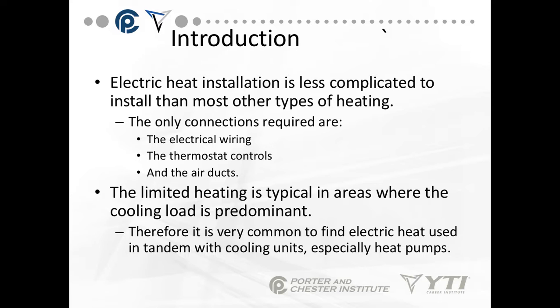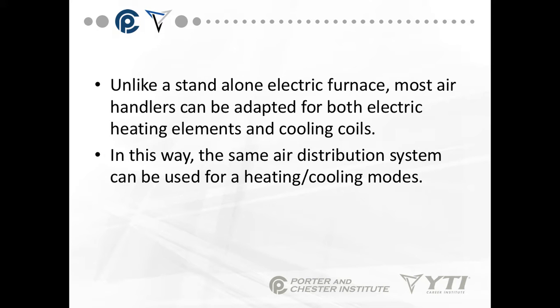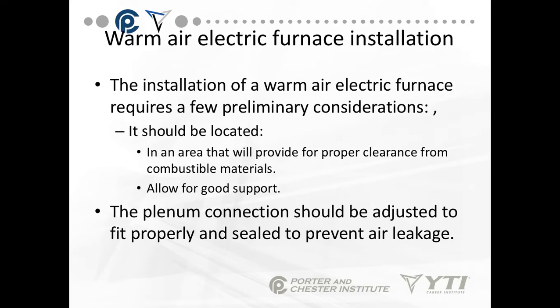Now, the heating is typical in areas where cooling load is predominant. In other words, areas in the southern part of the country where you don't have to have a lot of heating, but we do a lot of cooling. It's very common to find electric heat used along with cooling units, especially heat pumps. Unlike a standalone electric furnace, most air handlers can be adapted for both electric heating elements and cooling coils. In this way, the same air distribution system can be used for heating and cooling modes.